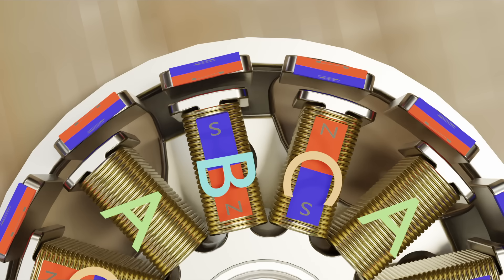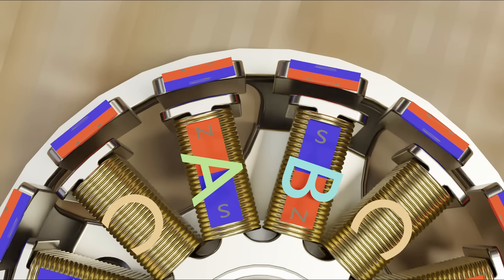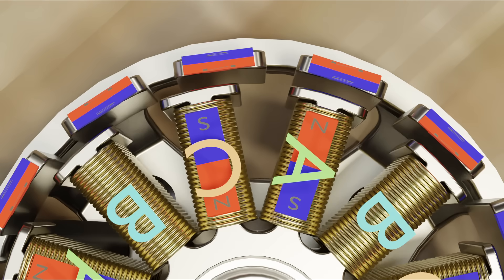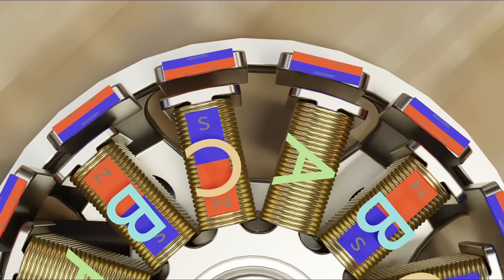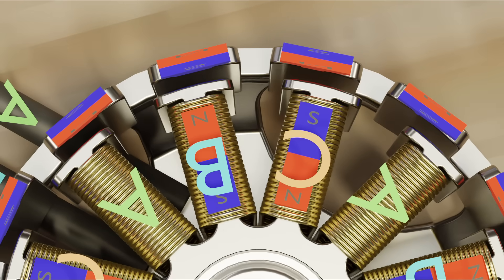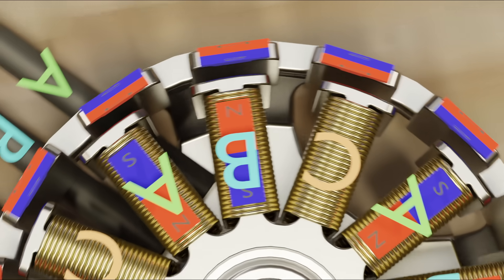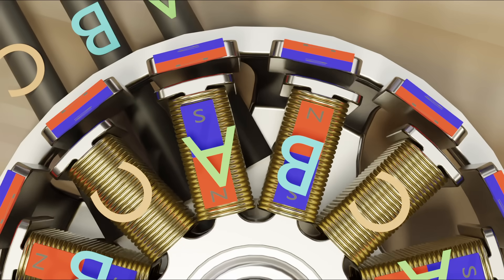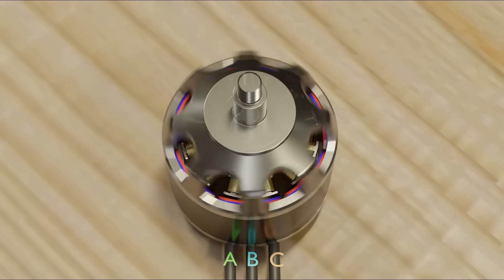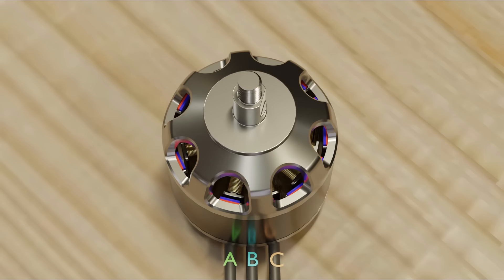This process continues with the next being running electricity into B and out of A, then into C and out of A, into C again and out of B, and finally into A and out of B. After this, we'd come back to the original phase, which is electricity flowing into A and out of C.